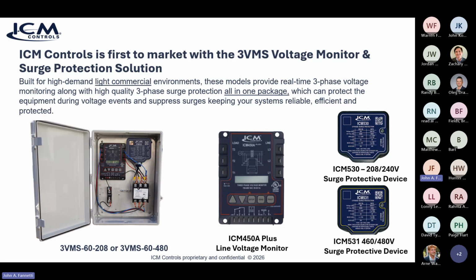Remember, the 450A by itself only breaks the control voltage. And then the 530 is an absorption product. It absorbs the surge. It doesn't break you from the service. Whereas if you have it all in one package, now if you get a voltage problem, the 450A will break you from the actual service voltage. Still with a surge, it's an absorption product. It absorbs the surge, dissipates it with the TMOVs that are inside, but that part of it won't take you offline.